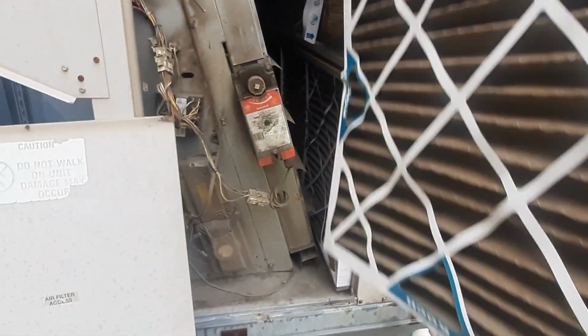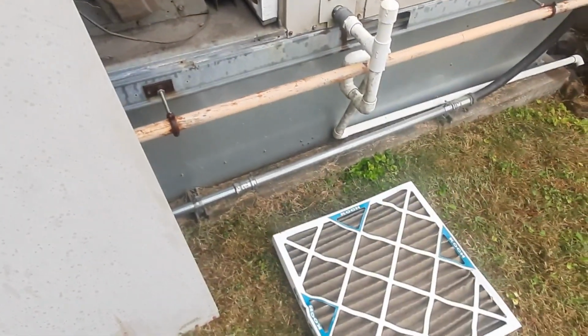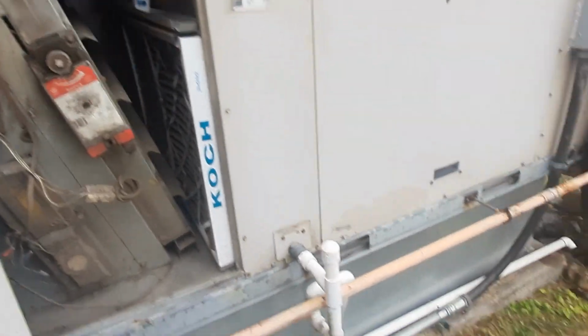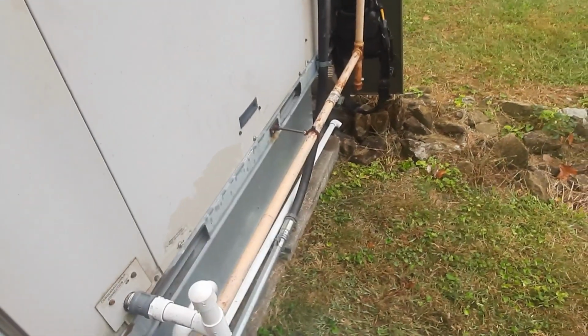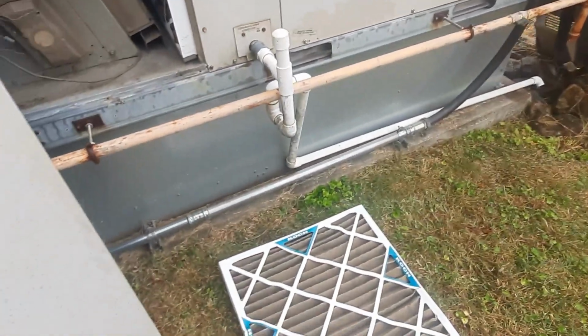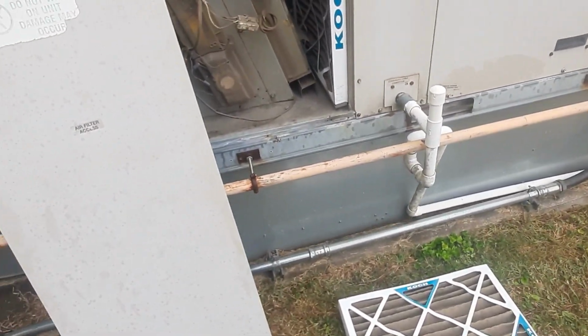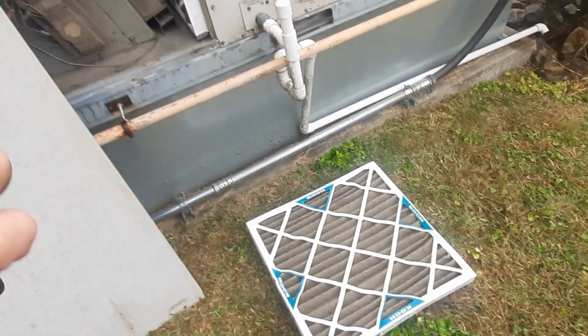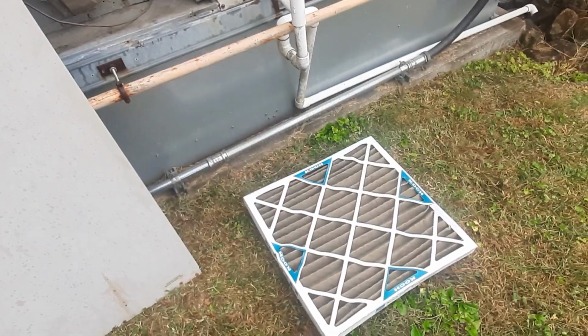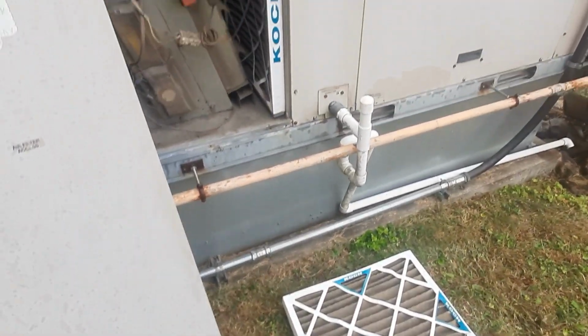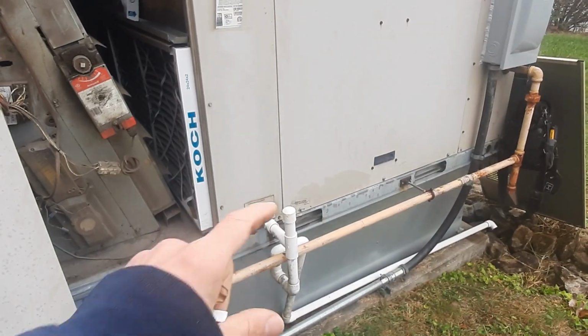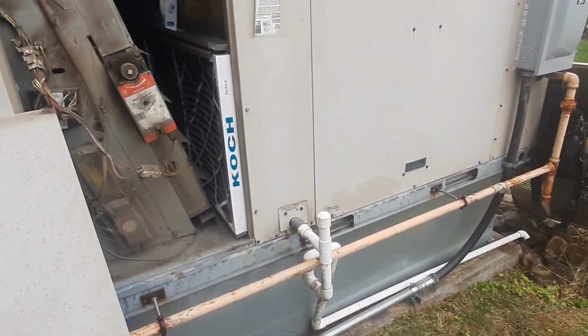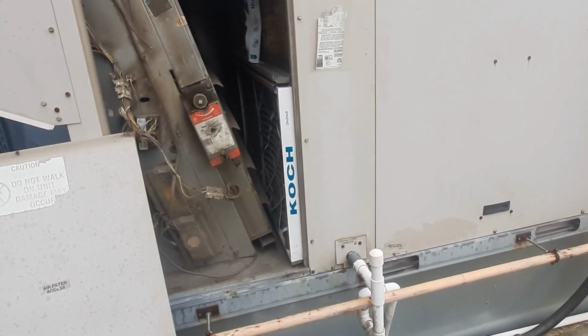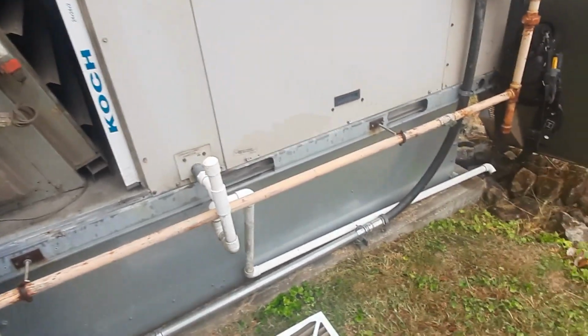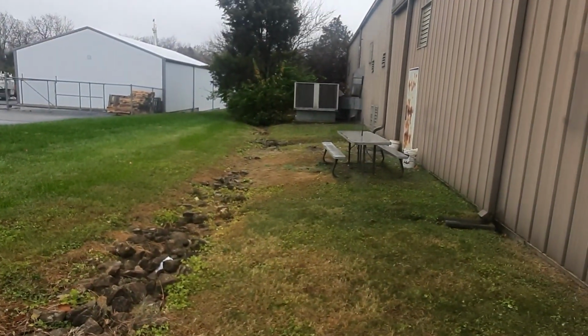Like I said, without those filters, we are due for a PM. These things kind of get neglected. We try to come back here and change the filters periodically, but this is not unusual. So anyways, I've got it locked out for high limit. Pretty sure we found our problem. I'll bet both stages fire off. We're going to go ahead and pull that panel, look at the belt, and at least temporarily I'm going to pull these filters out. We'll get the heat running and then go grab some filters. I'm sure the other one is going to be just as bad.